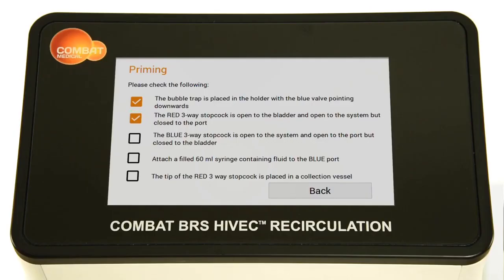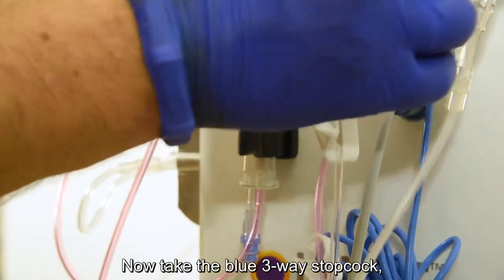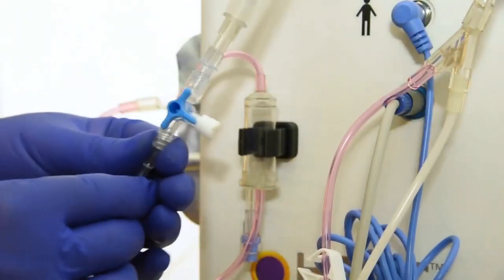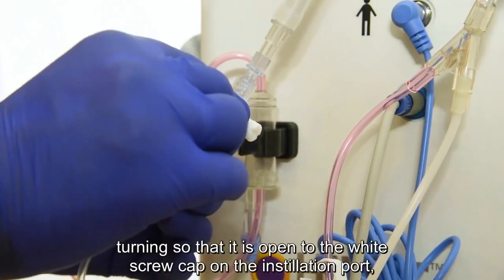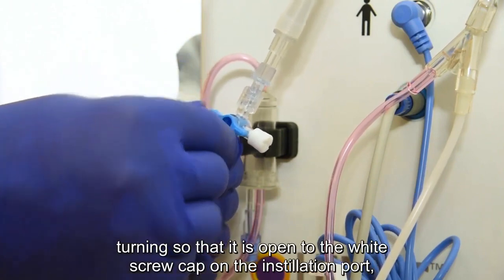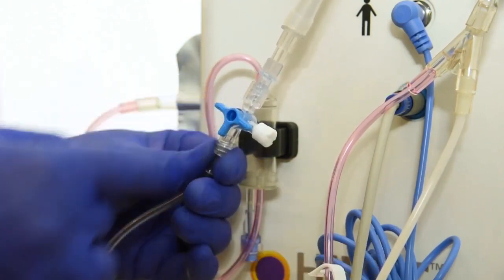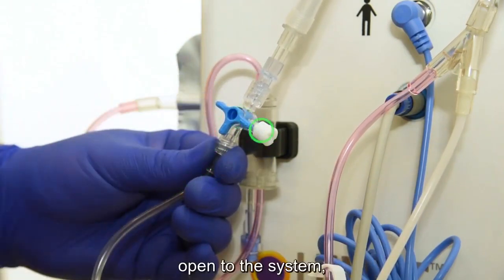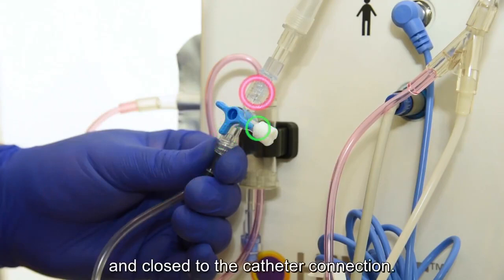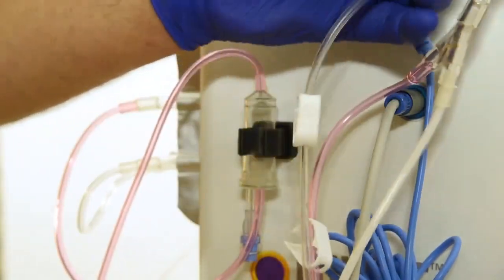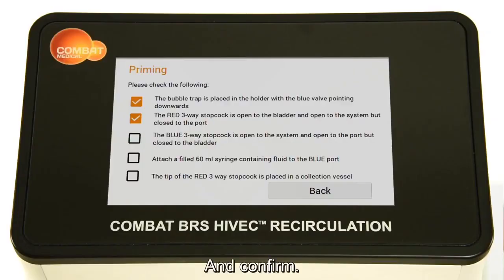And confirm. Now take the blue 3-way stopcock, turning it so that it is open to the white screw cap on the instillation port, open to the system, and closed to the catheter connection. And confirm.